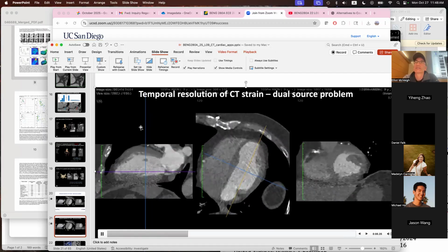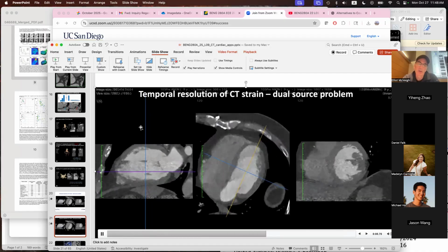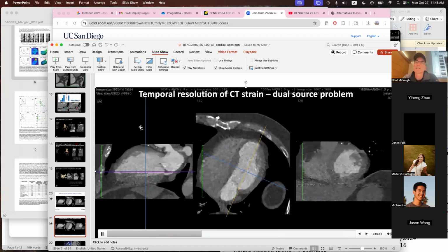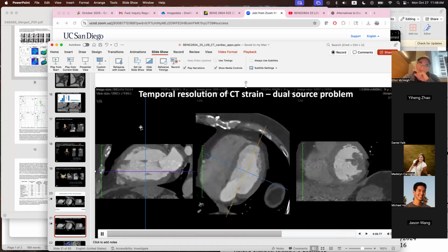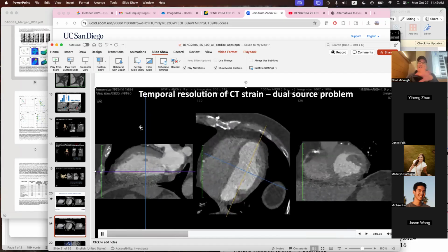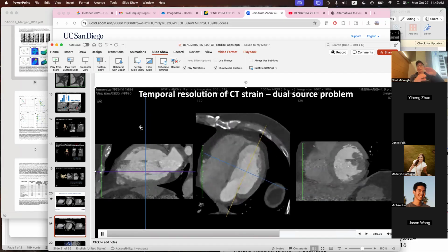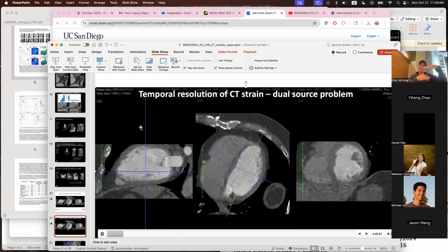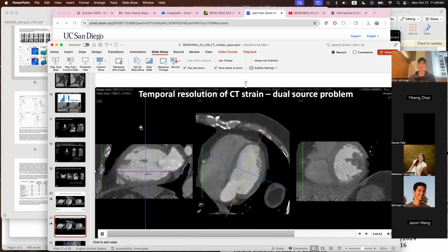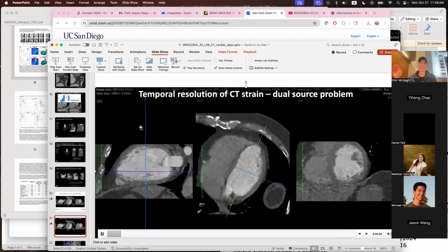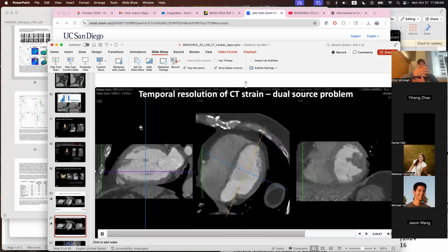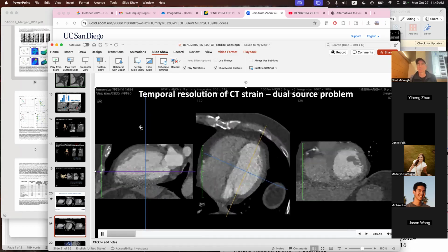Is it better not to? That's a great question. So, could you, if you knew what was going on here, correct this data to get rid of this step artifact? In certain instances, yes, you can correct it. And it involves a lot of interpolation between what is on either side of your detector. And Siemens came up with a product and they call it Z-free. It's basically they go in and post-process this data to try and realign everything, because it's such a problem.